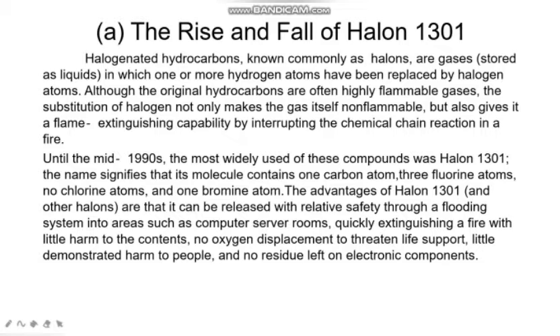Although the original hydrocarbons are often highly flammable gases, the substitution of halogen not only makes the gas itself non-flammable, but also gives it a flame extinguishing capability by interrupting the chemical chain reaction in a fire. Until the mid-1990s, the most widely used of these compounds was halon 1301. The name signifies that its molecules contain one carbon atom, three fluorine atoms, no chlorine atoms, and one bromine atom.